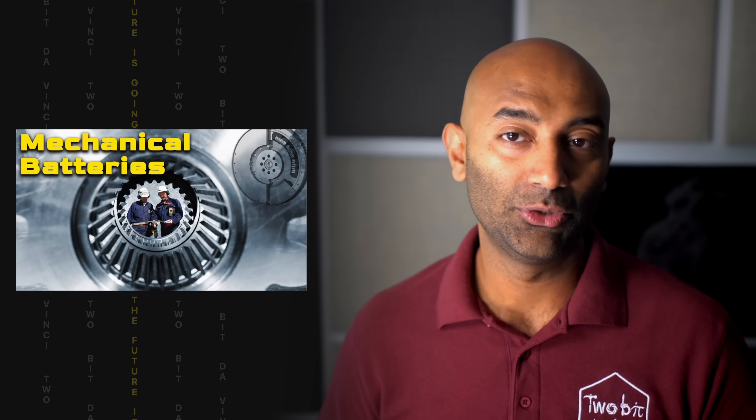This technology comes with a number of advantages over other energy storage. Where BEST could have one major advantage over pumped hydro is efficiency. Buoyancy energy storage's architectural simplicity means minimal energy loss during energy production, and the constant pressure head allows the pumps and turbines to operate at high levels of efficiency at all given times. Buoyancy energy could reach levels of between 85% and 95% efficient, compared to conventional pumped storage systems, which sit somewhere between 75% and 80%.